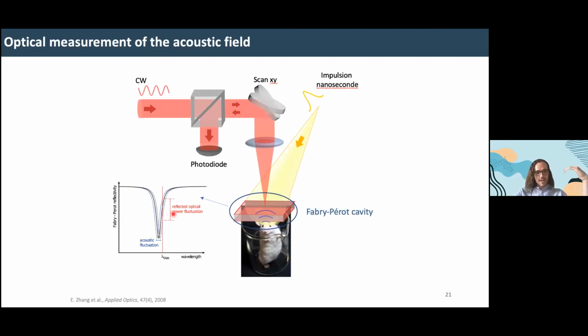These two facing mirrors have some peculiar interference effects, which give the following results. If you change the color, the wavelength, of this incoming reading beam, the amount of light that is reflected by those two facing mirrors, which you measure with the photodiode, will change. There are some wavelengths which are far less reflected by this Fabry-Perot cavity. Now if you fix the wavelength of this reading beam to a wavelength in the middle of the linear range, the really high slope here, you can see some acoustic effect, because the position of this dip depends on the thickness of the polymer layer. Whenever ultrasounds propagate through the polymer layer, they modulate its thickness, which in turn changes the position of this dip. So if you fix the wavelength here, a small change in the thickness of the polymer layer will result in a large change in the reflected light that you measure with the photodiode.